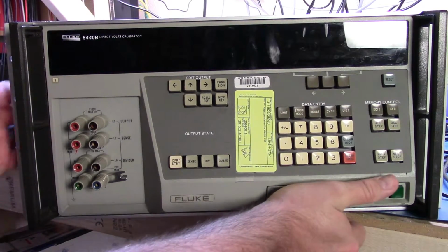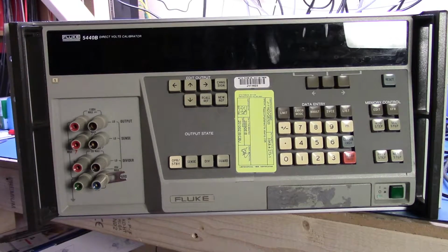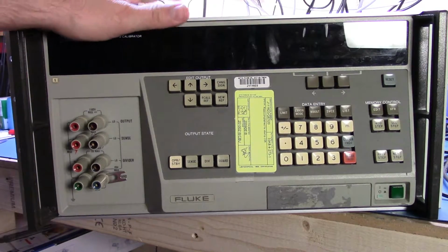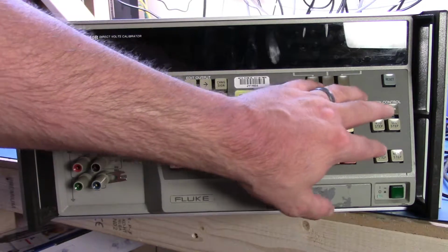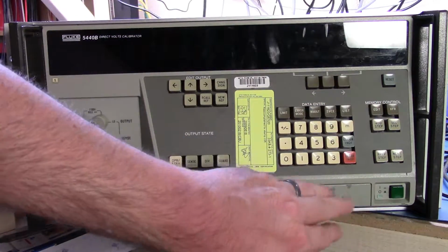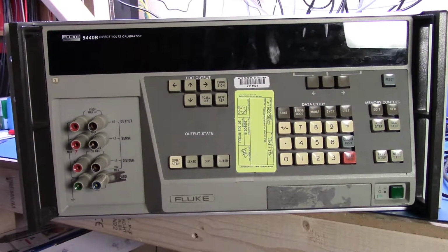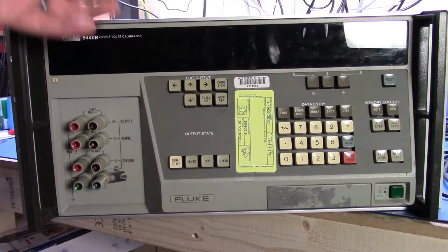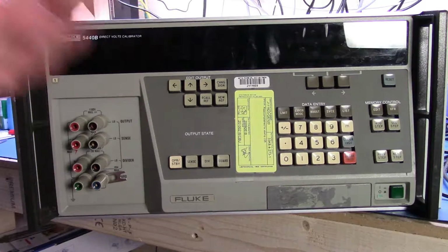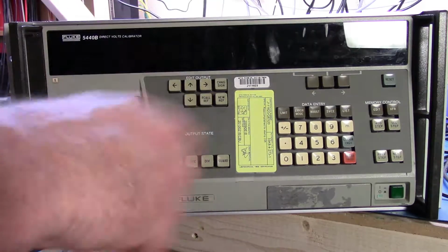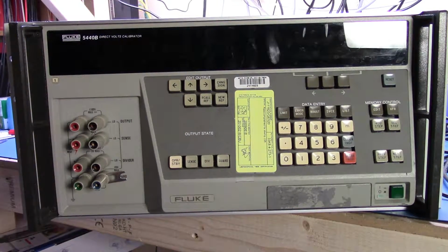What that lets you do is create your procedure, such as setting the voltage to this, then checking that, then checking this, entering it all into the device, and storing that procedure onto the memory module. Then you can come back, pull it back in, load it into the system, and run through that automated procedure.